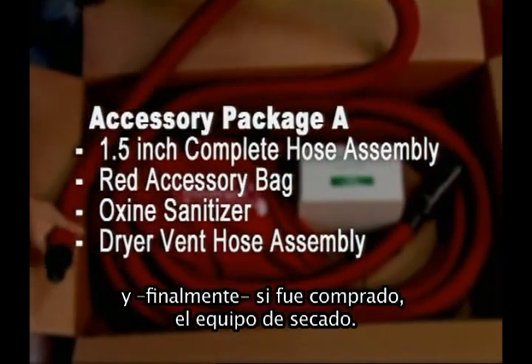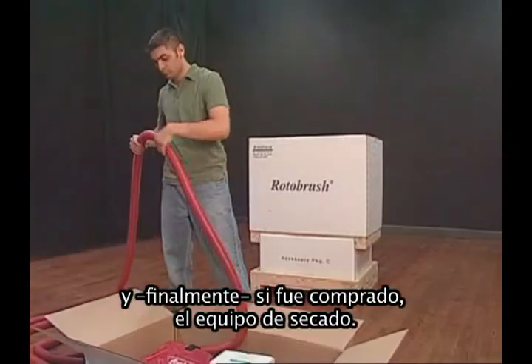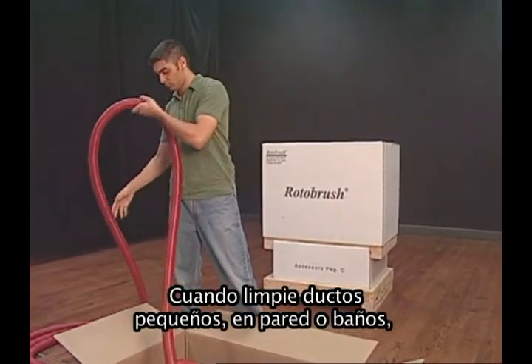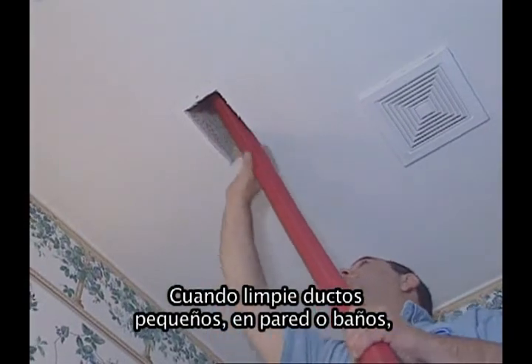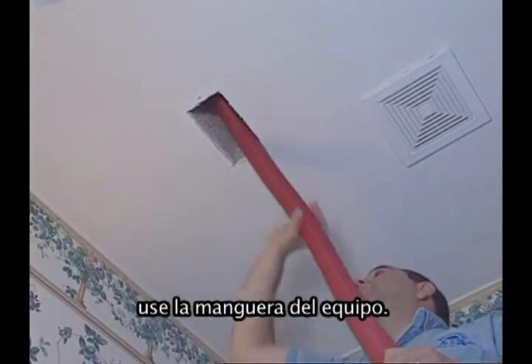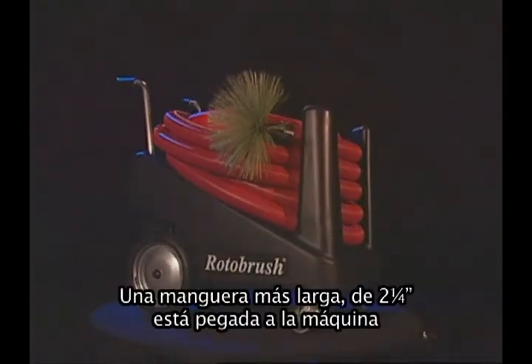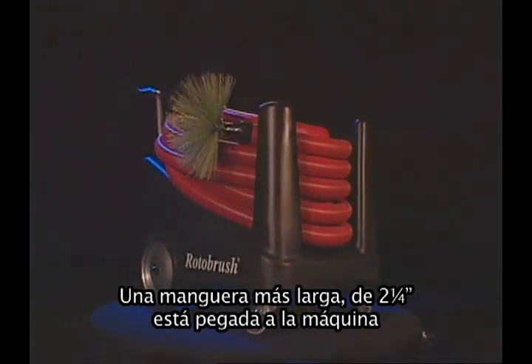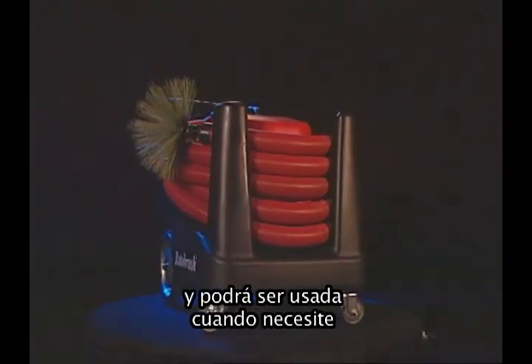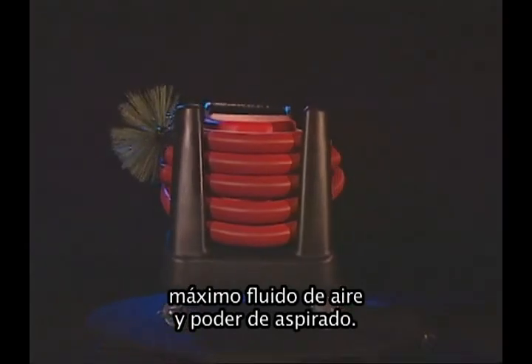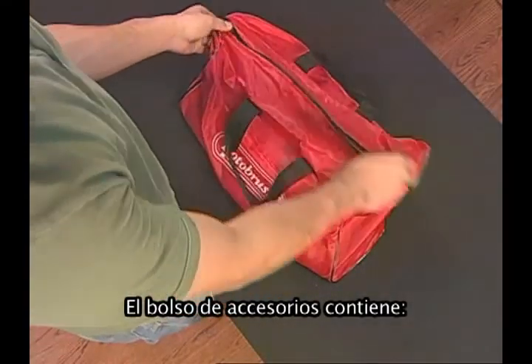and finally, if purchased, the dryer vent assembly. When cleaning smaller supply ducts, wall stacks, and 4-inch bathroom ducts, use the 1.5-inch hose assembly. A larger 2.25-inch hose assembly is attached to the machine during shipping and should be used whenever possible to provide maximum airflow and vacuum power. The red accessory bag contains the following.